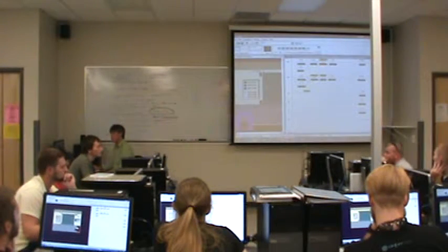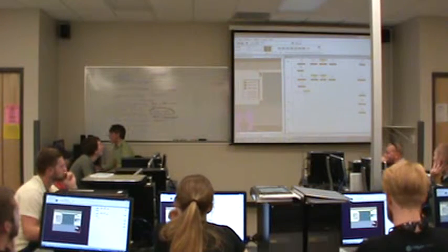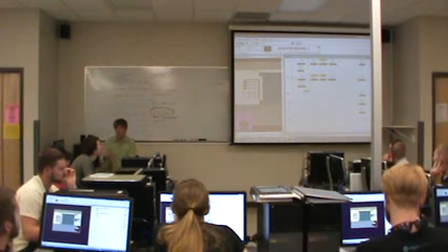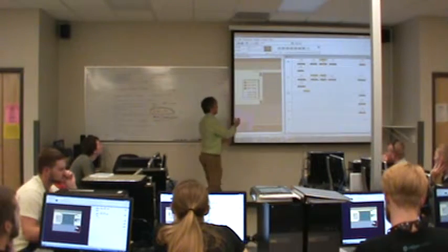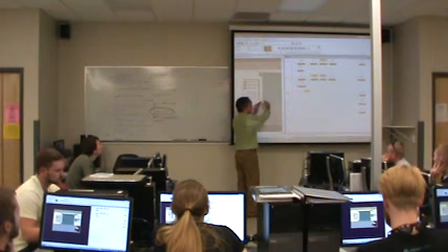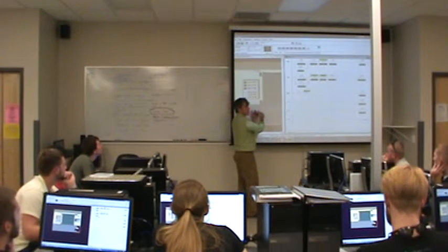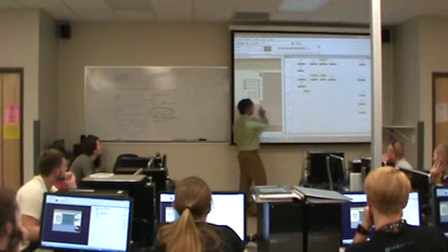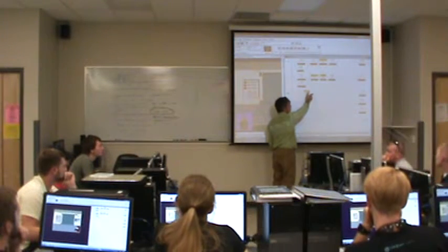Since both of these are normally open switches, I will have to use opposite contacts. In fact, I will want input 4 to be not made, right? It's a normally open switch, so when the door clears it, it will not be passing power. So there will be a 0 on bit 4. So that's the address I need to pass over here because I want to invert it.